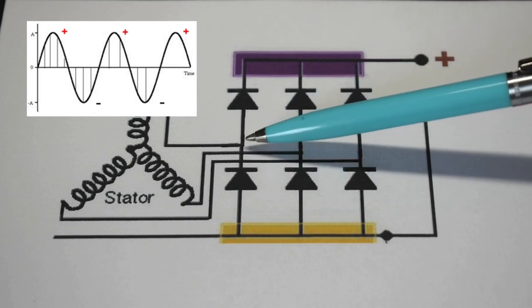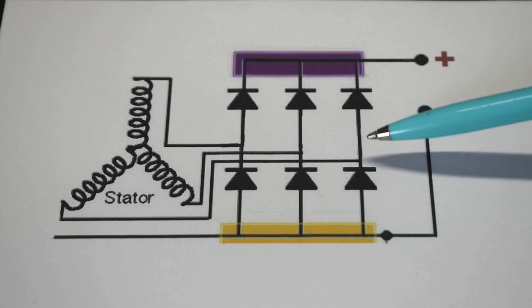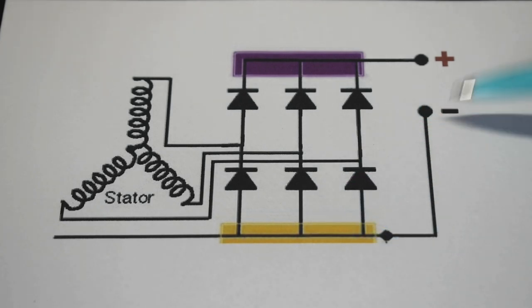And over here only the negative peaks are going to pass to the lower rail where the negative is. The power output from all three phases then goes into the voltage regulator which I showed you. And then before it leaves the unit you have a capacitor across the output that's going to smooth out any ripples in the direct current.